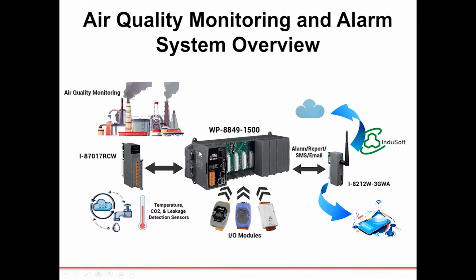In addition to that, it is a fully functional industrial controller, so it has lots of room to connect. If you want more direct I/O, it has lots of room for more I/O slots. You can also connect it over Ethernet and or RS-485, I believe, on this module, to other remote I/O modules in the system. For instance, temperature, CO2, and leakage detection sensors. So in addition to being the air quality monitoring and alarm system, this is also meant to be the brain of a lot of other industrial functions. And of course, one of the main advantages of our PACs is that they can multitask. They have enough processing to do a lot of different processes all at once.